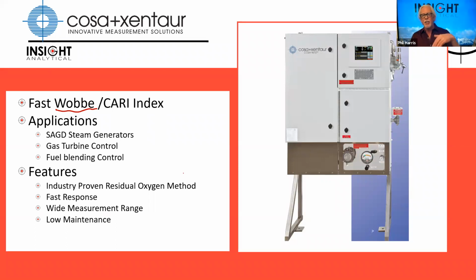In some applications, we've introduced a toluene backflush system where, when the amount of light going through the cell drops, the system automatically back-purges with toluene to clean the wax off. So it's application dependent, but generally we see single-digit months to many months between cell cleanings. And cell cleaning is literally 4 bolts off on each side and you've got the cell open.